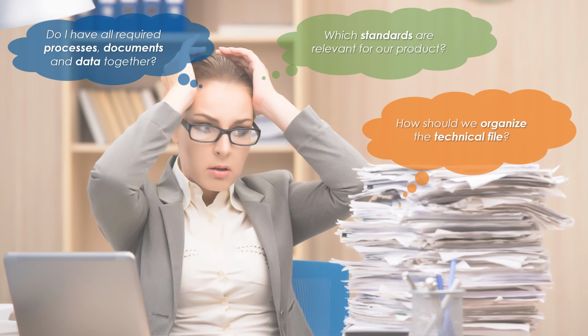When we look back on the requirements for QMS and the technical documentation, you should ask if your organization has all the required processes, documents, and data together. Often various information needed to fulfill the requirements of the IVDR is scattered throughout the organization. Also start identifying all relevant standards for your product so you can ensure conformity with the IVDR requirements, in particular when it comes to product realization. And think about how to structure your technical file in a way that allows maintenance during the complete product life cycle, but also enables an auditor to easily search and find information as proof for conformity.